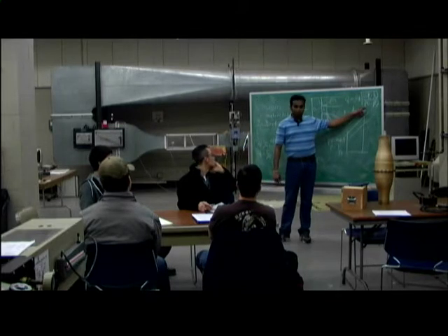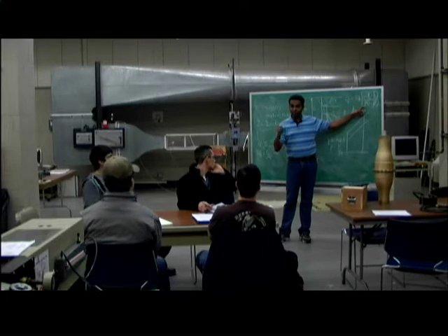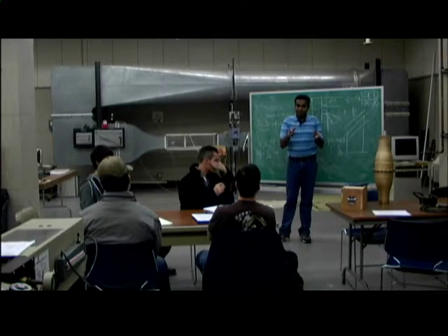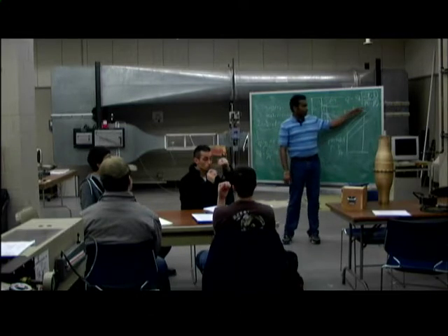That's the rho you have in that condition, not the atmospheric pressure but the pressure built up by the fan, because pressure is built inside the pipe system; it's a higher pressure than the outside atmosphere. Okay? So you take that pressure.